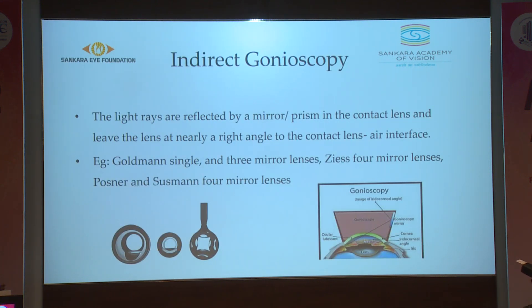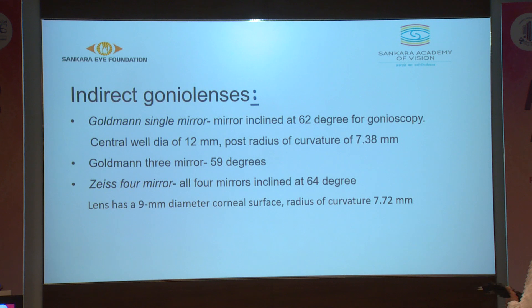That is why we use indirect gonio lenses, where light rays are reflected by a mirror or prism in the contact lens and leave the lens at nearly a right angle to the contact lens-air interface. The lenses used include Goldman single mirror, 3-mirror, Zeiss 4-mirror, Posner and Sussman 4-mirror lenses. The diameter of a Goldman mirror lens is larger than that of the Zeiss 4-mirror lens, which is why the Zeiss is able to perform indentation gonioscopy.